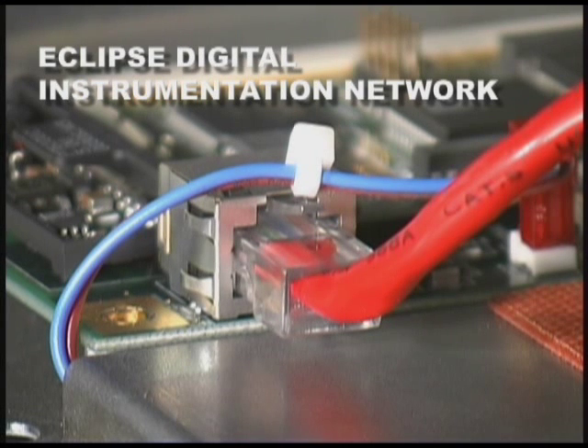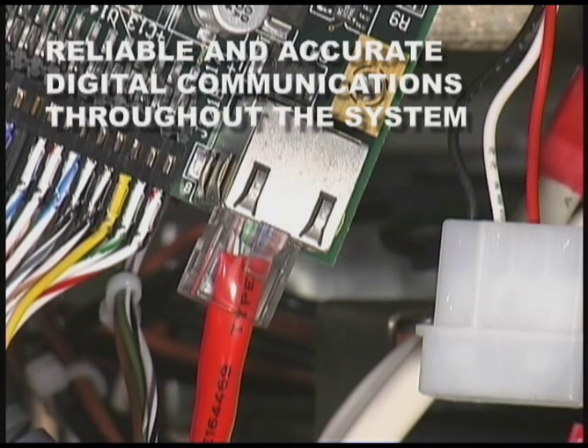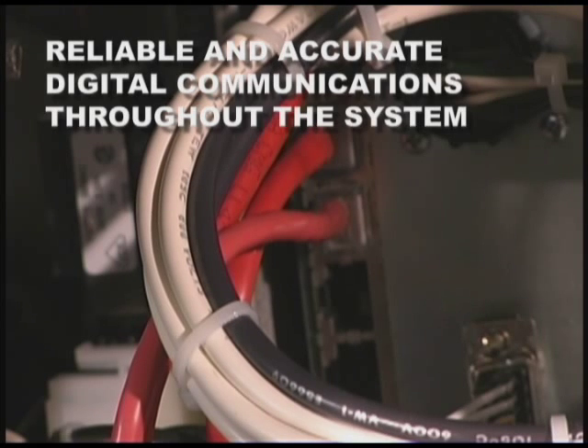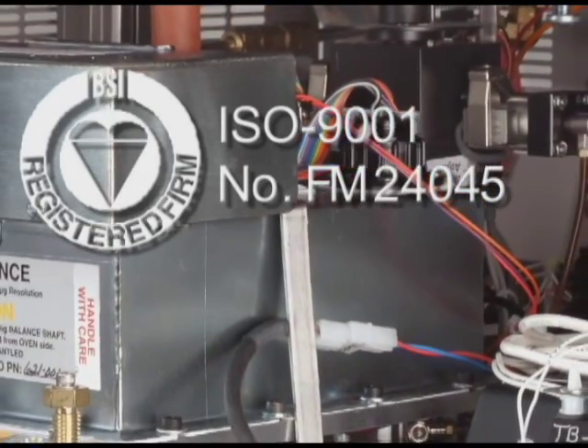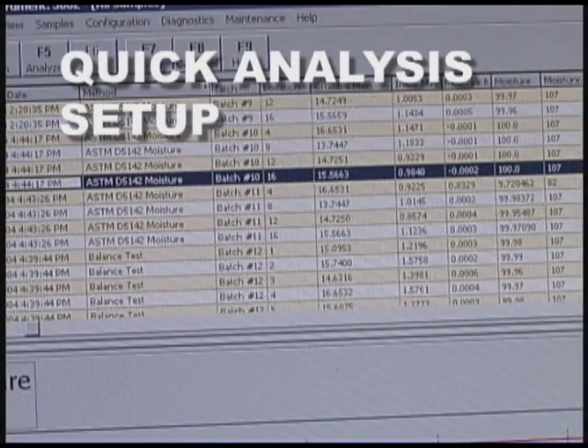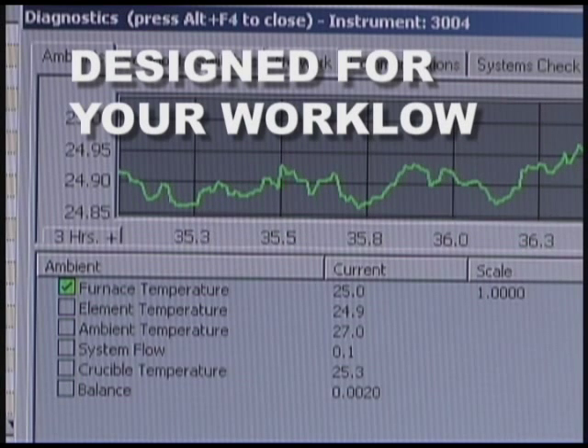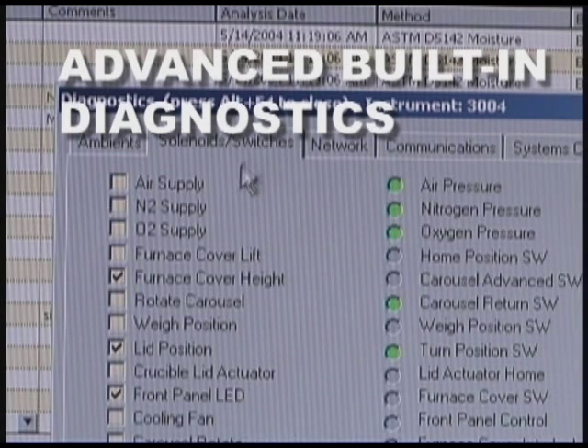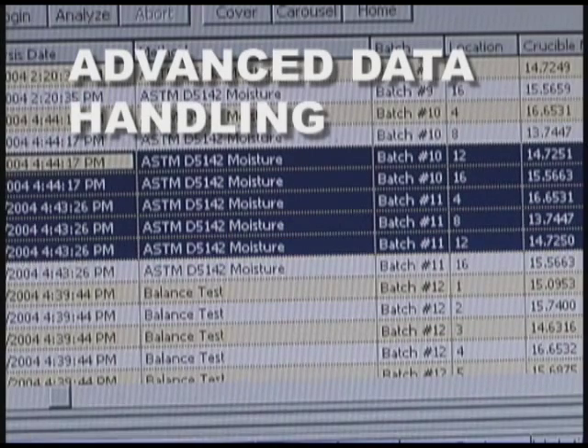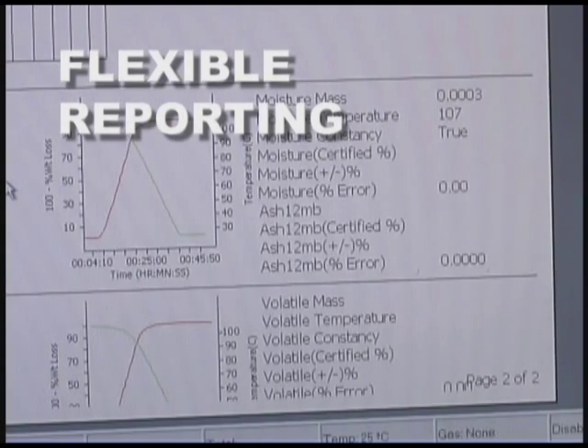The TGA 701 utilizes Leco's new Eclipse instrumentation network to provide reliable digital communications between all components. The Eclipse network offers enhanced reliability and rapid diagnostics. Leco's ISO 9001 certified design process ensures that the TGA 701 meets all FCC and CE requirements. The TGA 701 Windows application software controls up to two furnaces, offering flexible reporting and quick analysis setup. Customized data handling, graphing, and reporting provide results both quickly and automatically. The TGA 701 software supports compliance with FDA 21 CFR Part 11 for laboratories operating under FDA protocols.